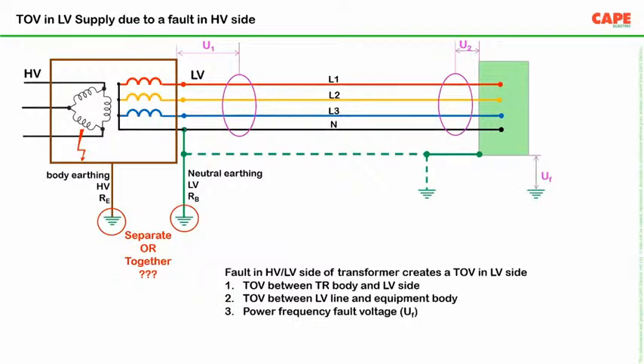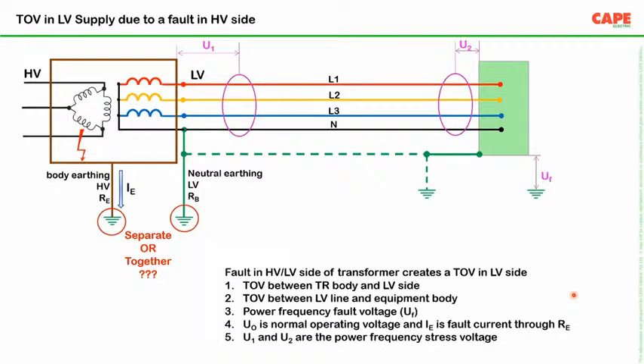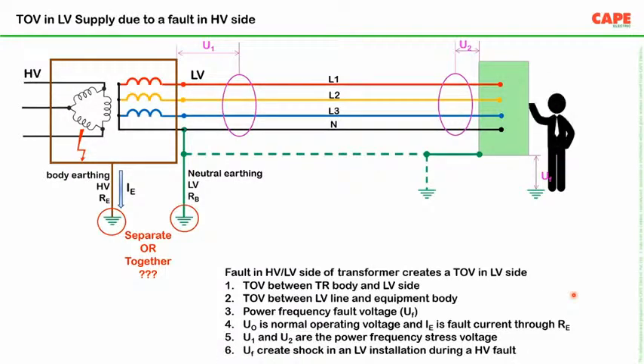Basically, the idea is, whatever you are doing, separate or together, the overvoltage U1 at the transformer, the overvoltage at the installation, and the power frequency fault voltage have to be reduced to less than a certain limit. This is the target. To achieve this target, the first question asked is what kind of low voltage system you are using: a TT system, TN system, or IT system. Now what are the tolerable limits and so on. This is the job of the designer. So we can follow both. Actually, I don't want to explain this in much detail because this itself takes a few hours.